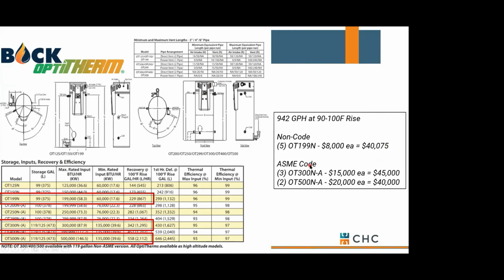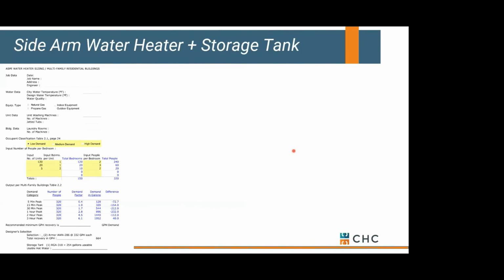I could also be looking at some ASME code versions of the same water heater, okay? Just a little bigger burner on them and a little more storage. Price-wise, I'm fairly close, but it depends on what the owner is looking for. Now, one thing that's important about tank type, typically they cannot be combined vented. Normally you're individually vented. So if you've got 5 tank type water heaters, you've got 5 vent runs leaving your mechanical room. Okay, just something to keep in mind. Now I'm going to get to a summary at the end here, so don't worry, don't stress out.